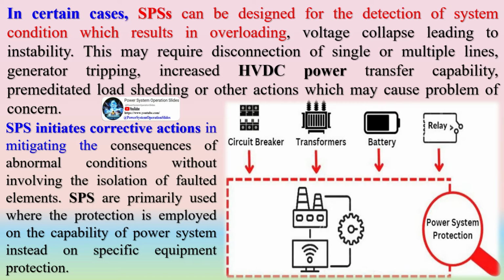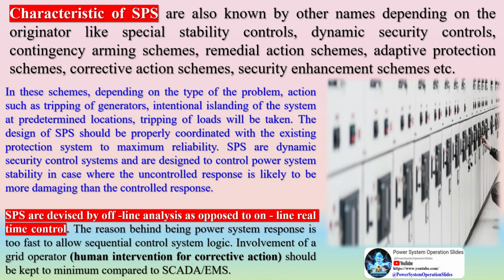During contingency conditions, SPS can be used as a tool for maintaining overall satisfactory operation of the power system. SPS can be installed to maintain frequency deviation during post-contingency, and it is referred to as frequency control SPS, or to prevent the system from voltage collapse or overloading of thermal limit, and it is referred to as network control SPS. In certain cases, SPS can be designed for the detection of system conditions which result in overloading, voltage collapse leading to instability. This may require disconnection of single or multiple lines, generator tripping, increased HVDC power transfer capability, premeditated load shedding or other actions which may cause problems of concern.